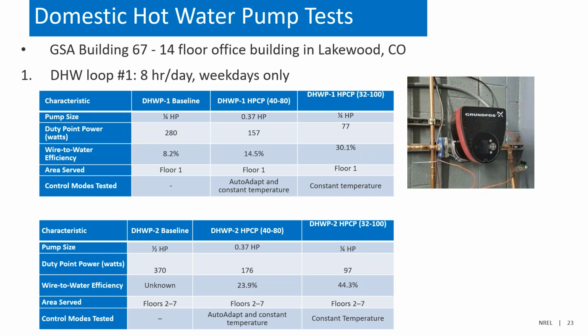So just really quick going through the duty point power numbers, you'll see that for both of these, we had very significant reductions in power draw. So the duty point power is essentially how much power the pump is drawing at the peak flow rate and differential pressure that the system sees. And so for the domestic hot water pump number 1, we saw about a 44% reduction in peak power with the first one, and then with the second one, it was about 72%. So even if these pumps would have just run at 100% speed, you're still getting on the order of 72 to 44% energy savings there. So essentially it's showing these are way more efficient than the current pumps.